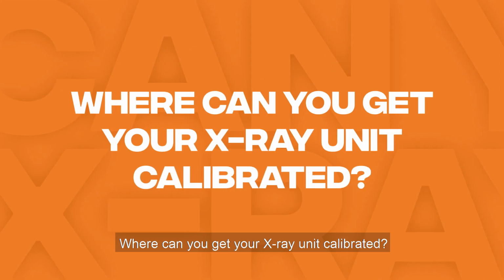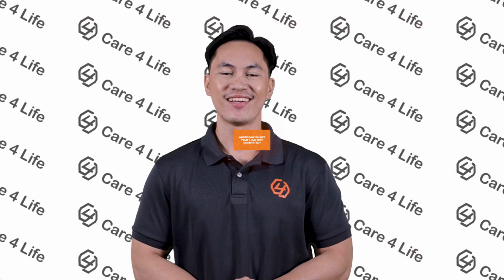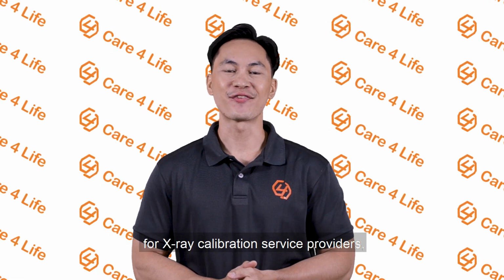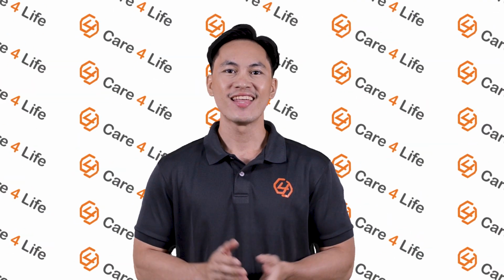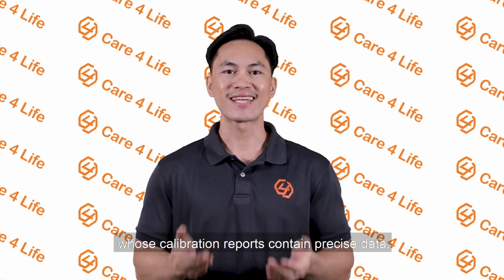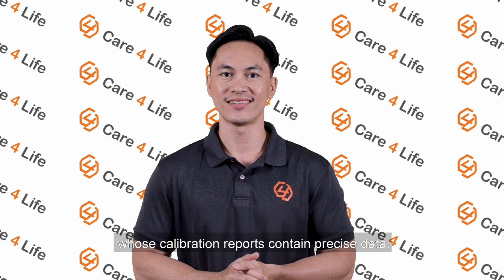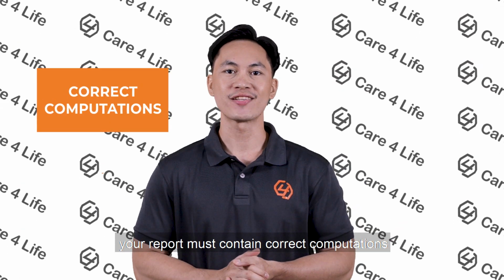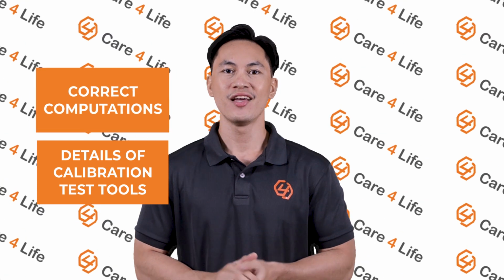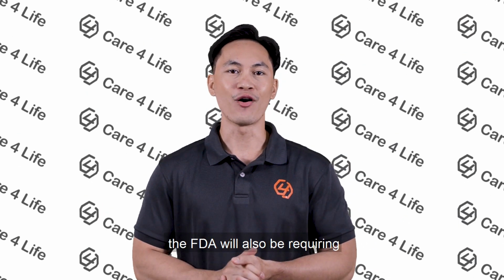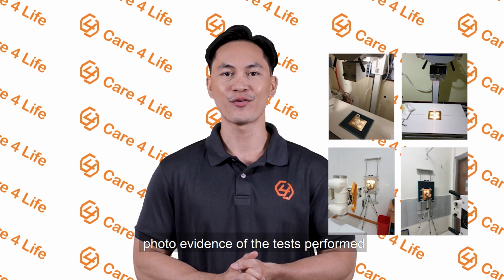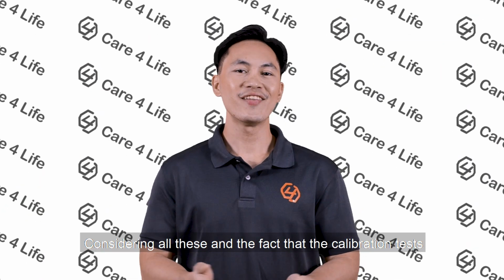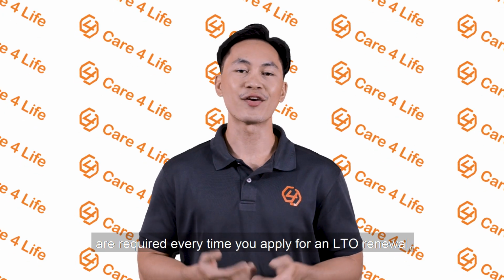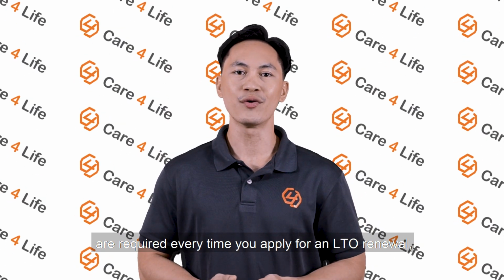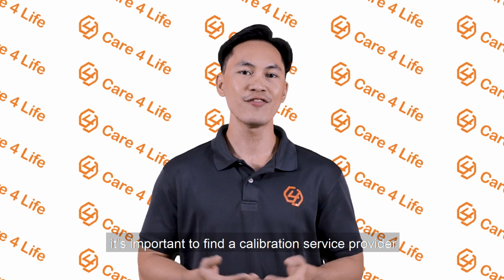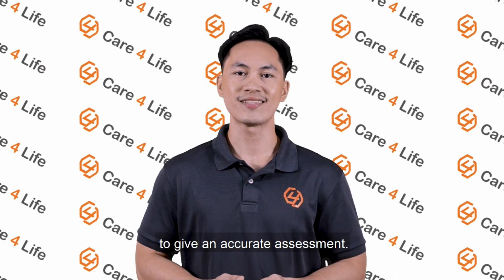Where can you get your X-ray unit calibrated? While the FDA doesn't provide accreditation for X-ray calibration service providers, they only approve LTO applications whose calibration reports contain precise data. Your report must contain correct computations and details of the calibration test tools. To prove the test validity, the FDA will also be requiring photo evidence of the tests performed. Considering all this and the fact that the calibration tests are required every time you apply for an LTO renewal, it is important to find a calibration service provider you can trust to give an accurate assessment.